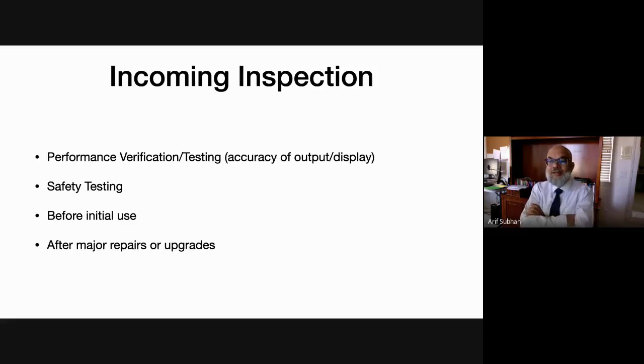Also, when you do major repairs or upgrades to a device, you need to do some kind of performance testing. It's not called incoming inspection at that time. It's called performance verification and safety testing. Because when you open up a device, you may be making changes, upgrades, or replacing major components. You need to make sure after you put the pieces together, you are testing the device to make sure that it's performing according to specifications.